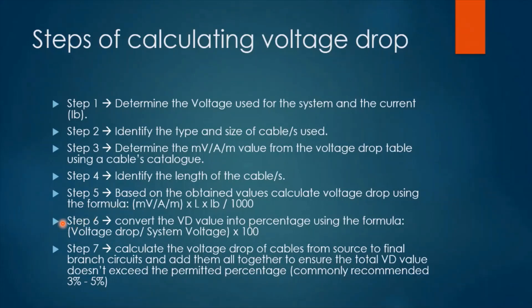Step six: convert the voltage drop value into a percentage using the percentage formula. Step seven: calculate the voltage drop of cables from source to final branch circuit and add them all together to ensure the total voltage drop value does not exceed the permitted percentage, which is recommended between 3% and a maximum of 5%.